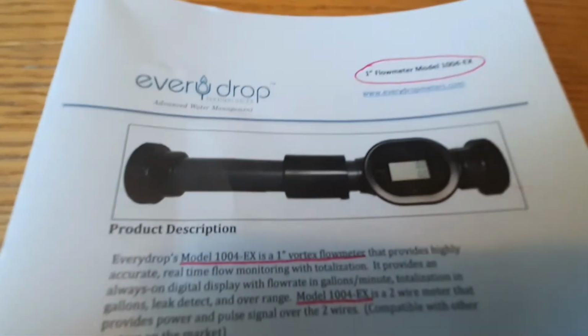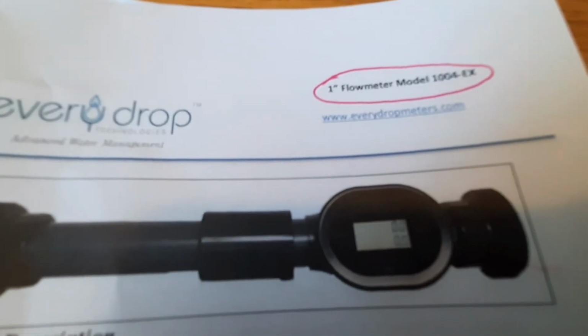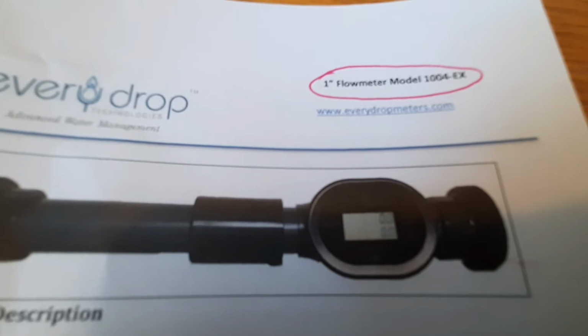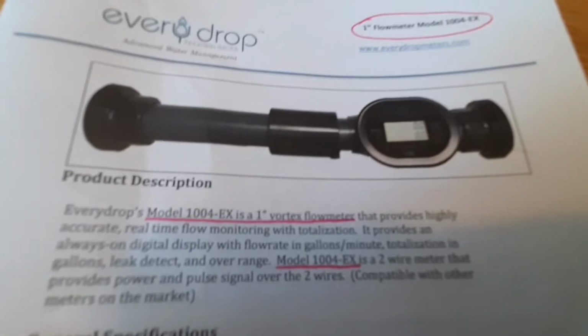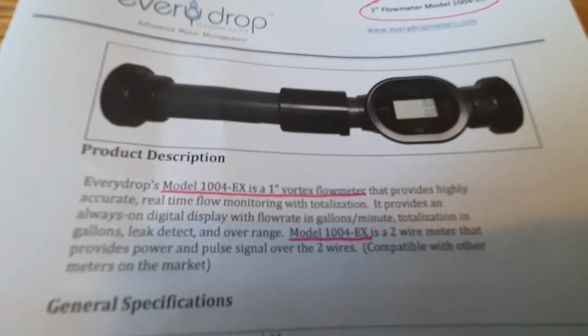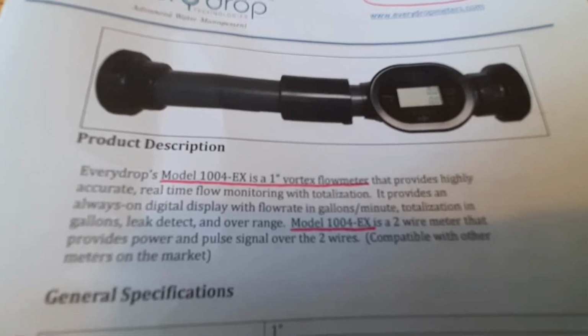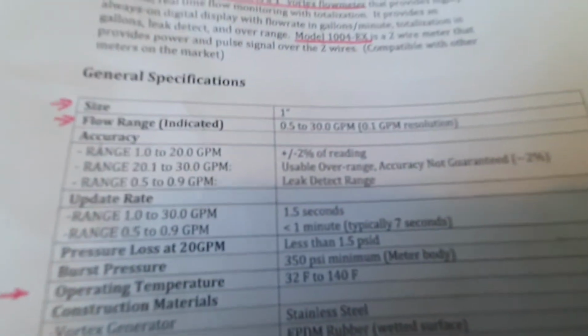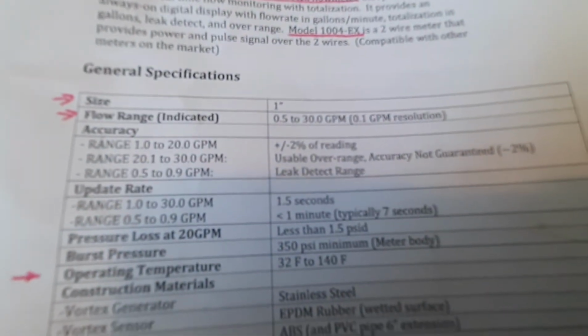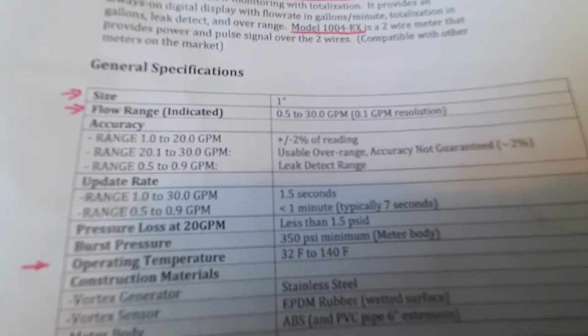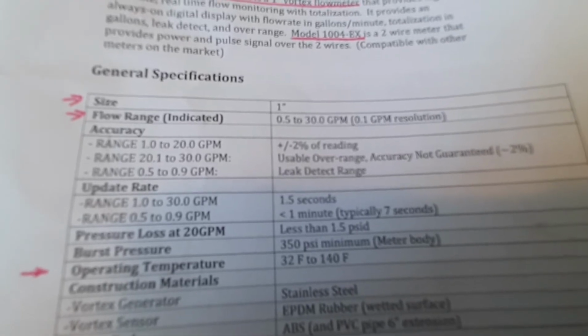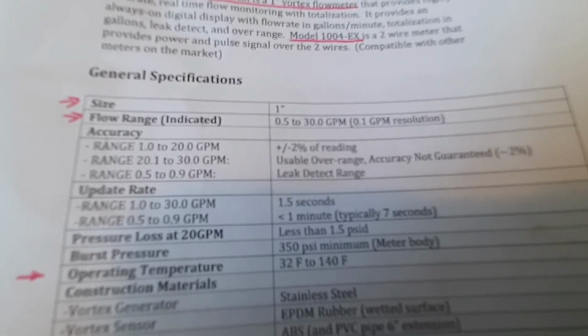So that's one thing. The second thing I want to briefly talk about is the Everydrop model 1004EX. It's a 1-inch flow meter - this is how it looks. It's a vortex flow meter with 2 wires, hardwired. It's a 1-inch pipe, and the flow range is between half a gallon to 30 gallons per minute.